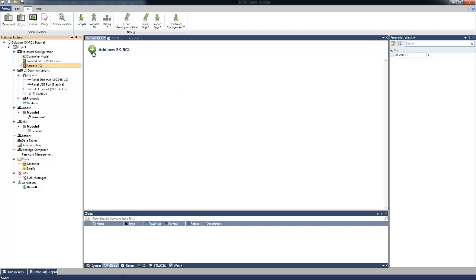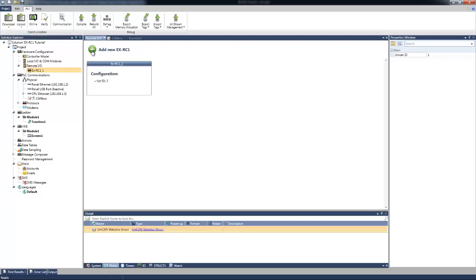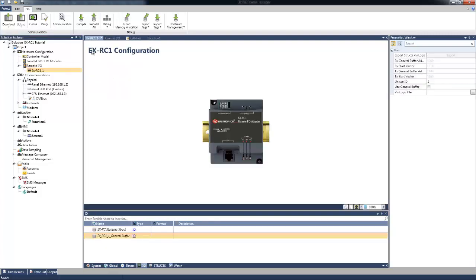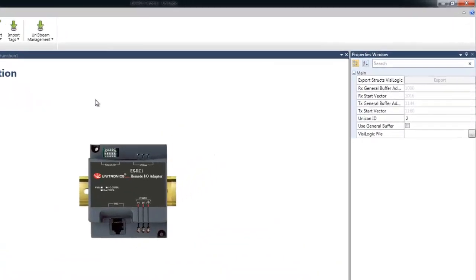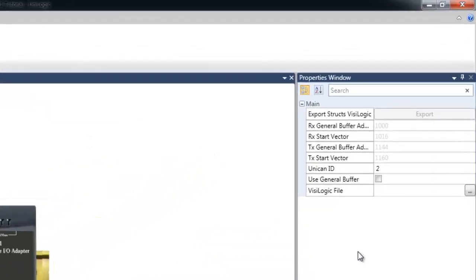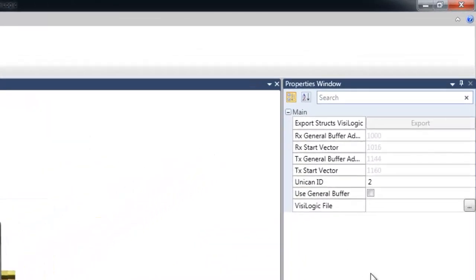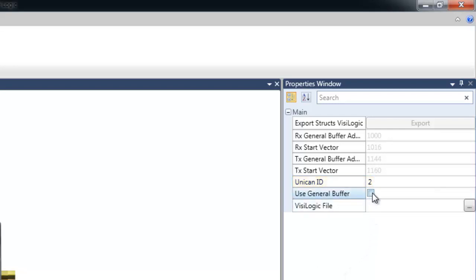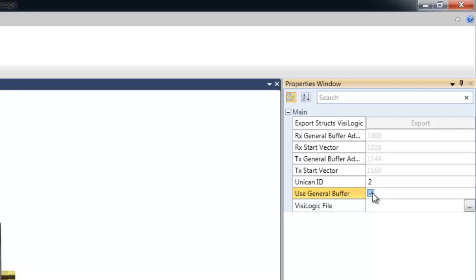Now, we'll click Add New EXRC1. In the Properties window, we can set the EXRC1 ID. We'll leave it as 2 and select the General Buffer checkbox, which enables us to exchange another 16 registers to and from the EXRC1.